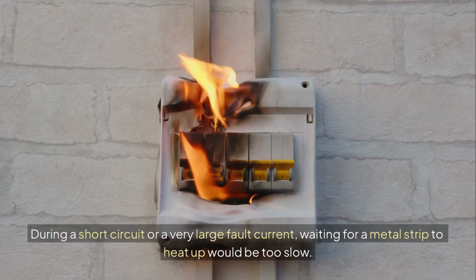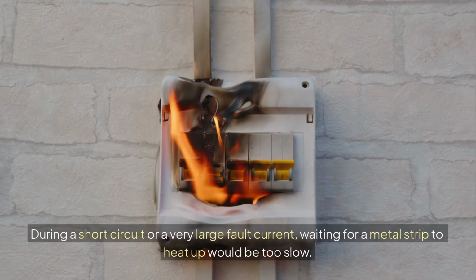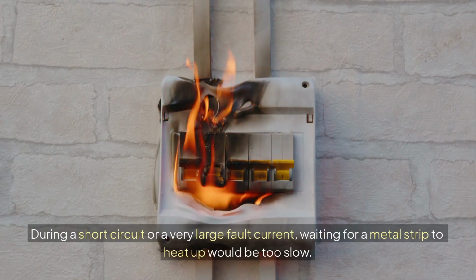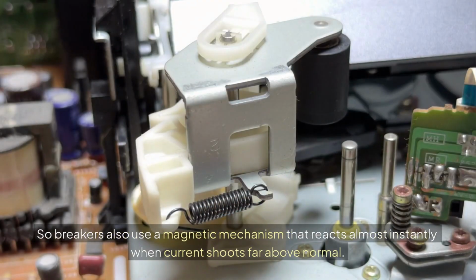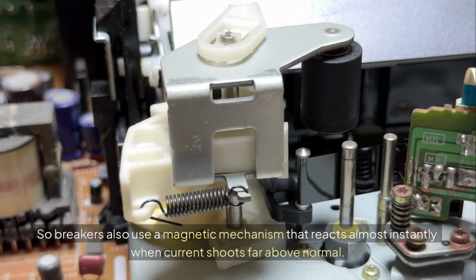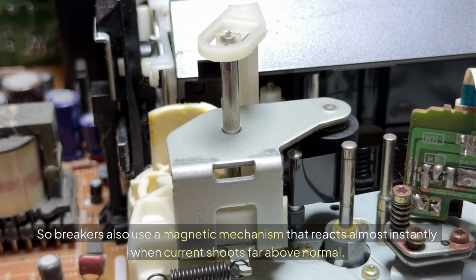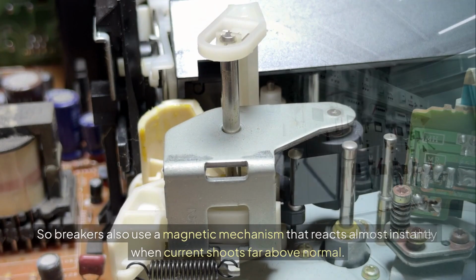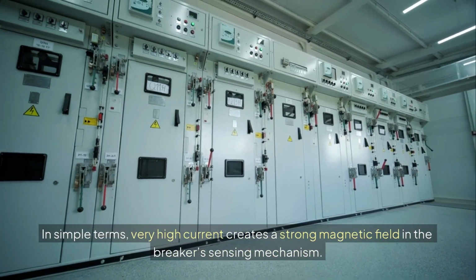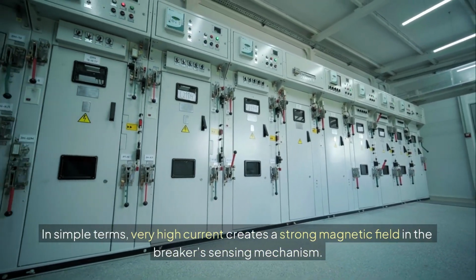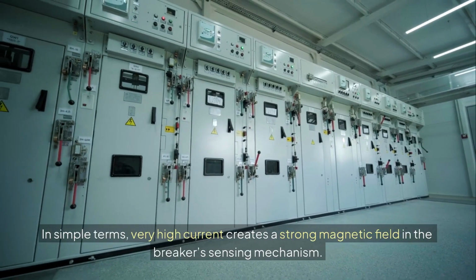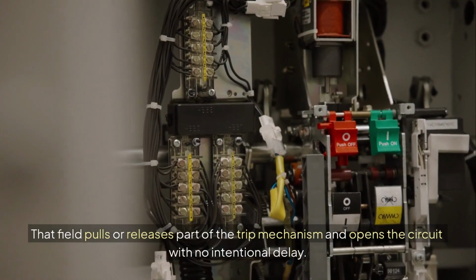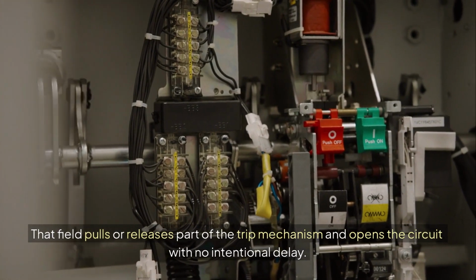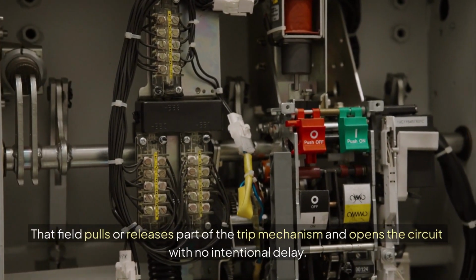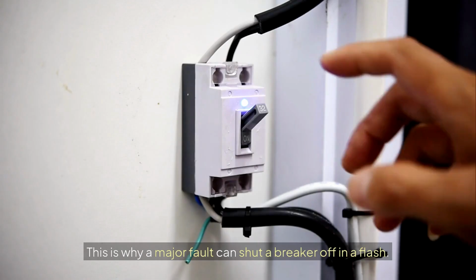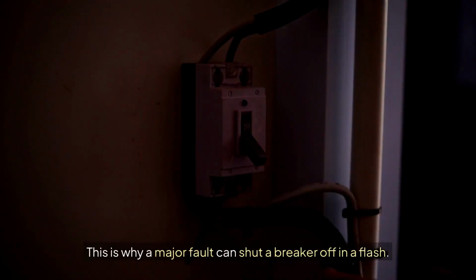The magnetic trip: this is the fast one. During a short circuit or a very large fault current, waiting for a metal strip to heat up would be too slow. So breakers also use a magnetic mechanism that reacts almost instantly when current shoots far above normal. In simple terms, very high current creates a strong magnetic field in the breaker's sensing mechanism. That field pulls or releases part of the trip mechanism and opens the circuit with no intentional delay. This is why a major fault can shut a breaker off in a flash.